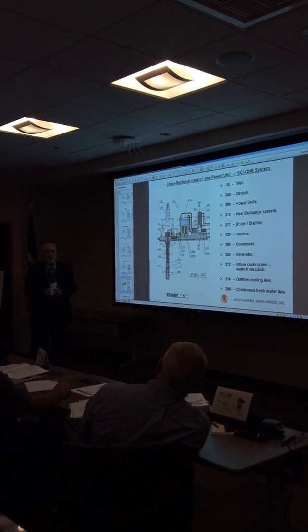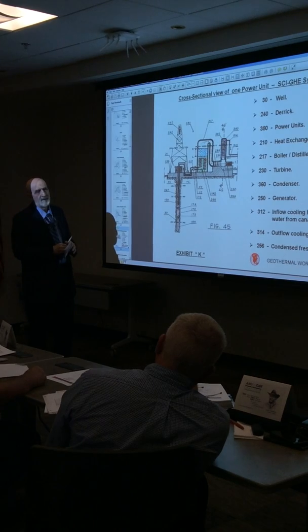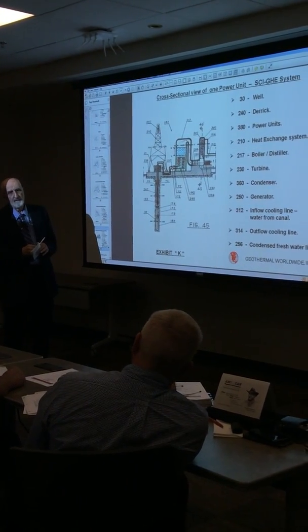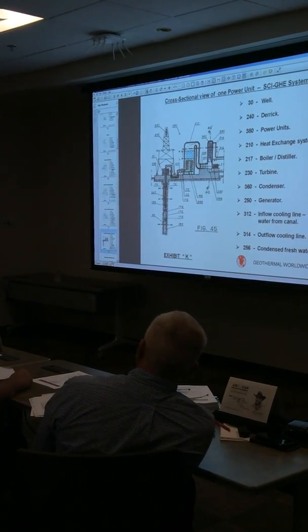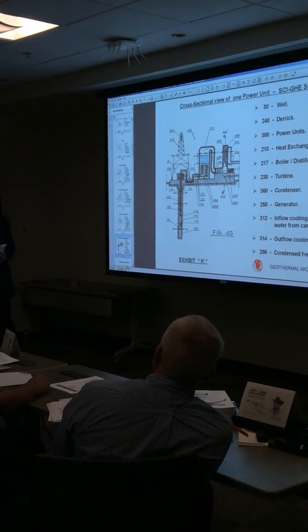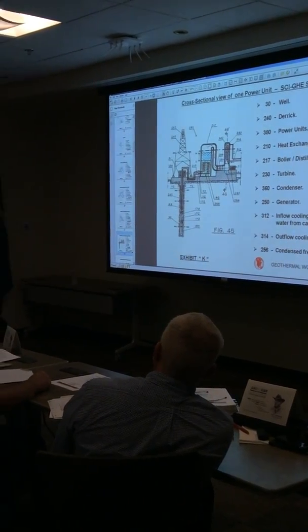Okay, you talked about bringing it up. Your temperature's probably 450, 500 degrees there. You drop that temperature down, you're going to end up with significant precipitation going back down the wellbore. How do you deal with that? Okay, for those who don't understand, he's talking about heat flux. The rocks will get cooler if you're extracting heat, so you need time to replenish it.